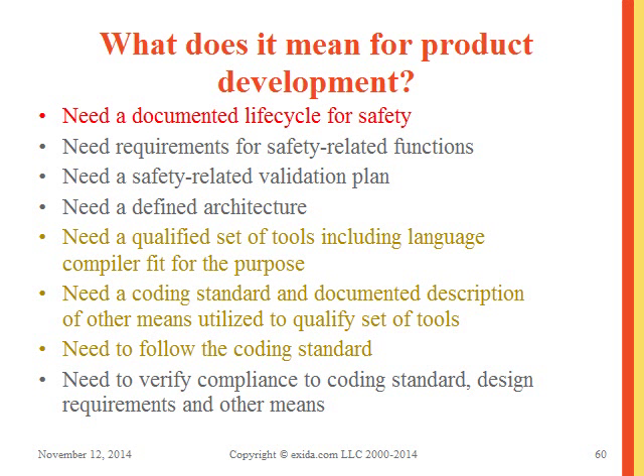For product development, you need a documented safety lifecycle, requirements for safety-related functions, a safety-related validation plan, a defined architecture such as 1oo1 or 1oo2, a qualified set of tools including language compiler fit for purpose, a coding standard, and verification of compliance to coding standards and design requirements. Not all of these requirements need to be met for simple mechanical devices, but the ones that do still need to be met.